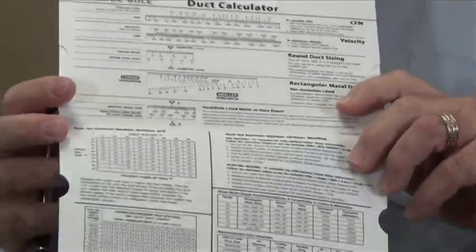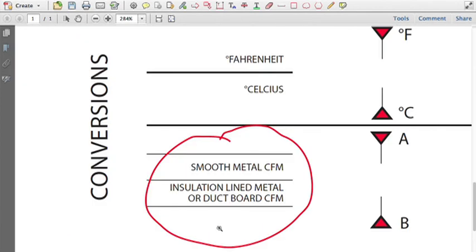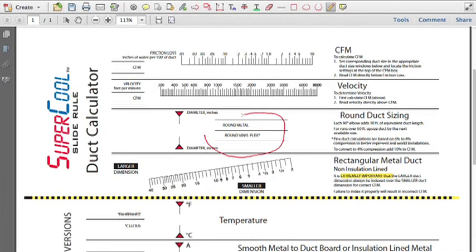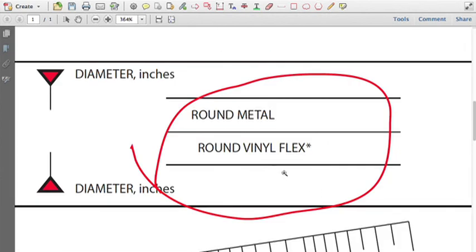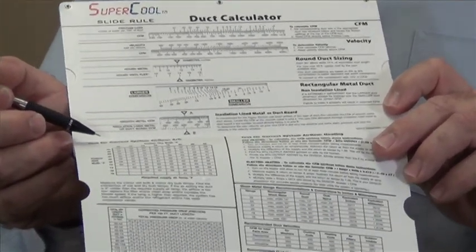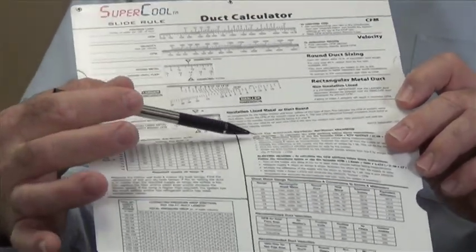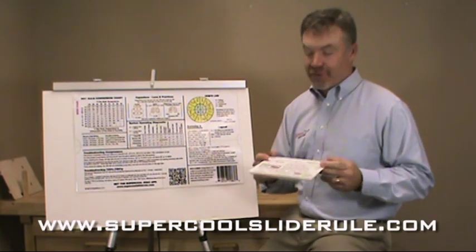Inside, it has the only direct reading conversion from smooth metal duct to insulation lined metal duct. This is imperative — you must have this. There's not another one out there that I've ever seen. It has direct reading of round vinyl flex duct versus round metal duct, so you can calculate anything you want with a duct calculator. It's here. You can also test for correct system airflow through an air conditioning or heating system. Pressure drops — this tool will save you countless hours of frustration.